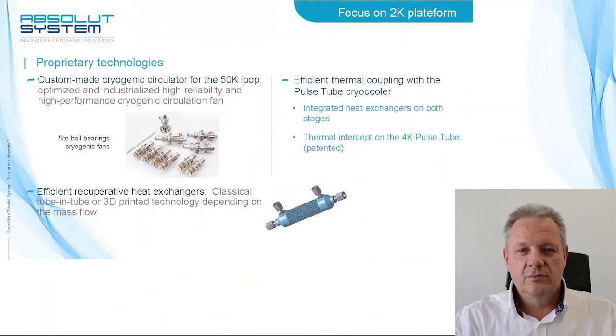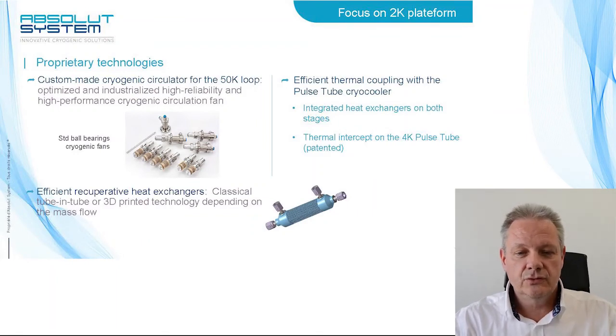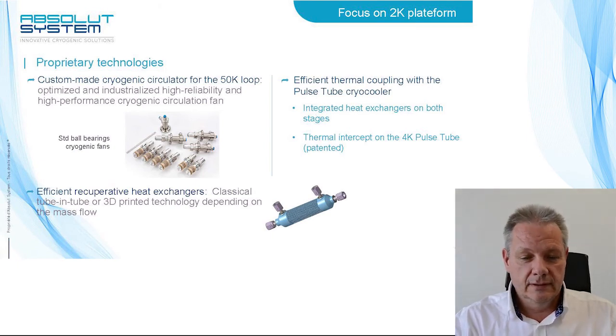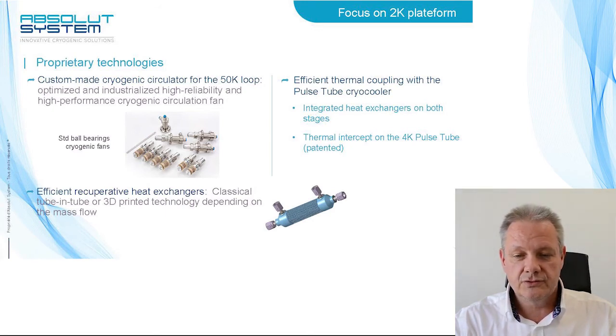In the 2K XCube platform, we have three different tailored technologies. First, we use a custom-made high-reliability and high-performance cryogenic circulation fan, designed, optimized, and produced by Absolut System. Then we have efficient recuperative heat exchangers, tube-in-tube or additive manufacturing technologies, depending on the mass flow. Finally, efficient thermal coupling with the pulse-tube cryocooler is achieved thanks to an incorporated heat exchanger or thermal intercept.